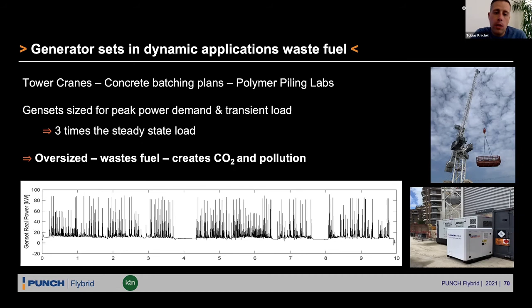So what we have done is create an energy storage device with a flywheel in it. We call it the Punch Power 200, and it injects energy from the flywheel when needed. The flywheel is very good at injecting energy at high power, almost instantaneously. We can go from 0 to full power in 30 milliseconds, and we can do that millions of times without degrading.